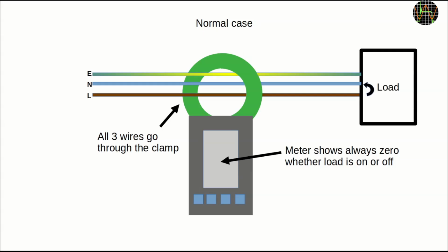If you clamp all three conductors, which is the same as if you just clamp the cable without removing the outer insulation, you will normally measure just 0, regardless of whether there is current flowing to the load or not. This is because the current in the L wire is the same as the one returning in the N wire, but coming from the other side, the two magnetic fields cancel each other, and since there is no current in the E wire, a clamp meter around all three conductors will just show the total, which is 0. It is important to understand that in such a measurement, 0 doesn't mean no current is flowing. There could be hundreds of amps, but for the clamp meter they cancel each other.